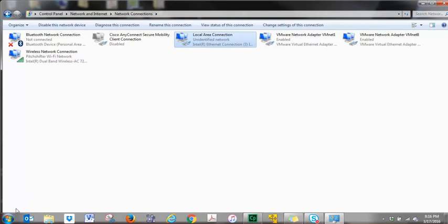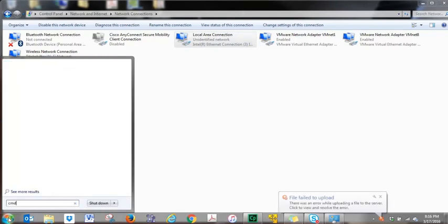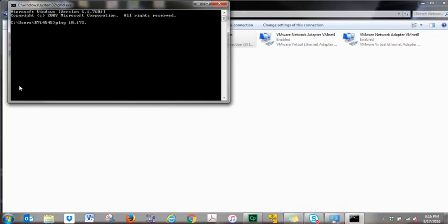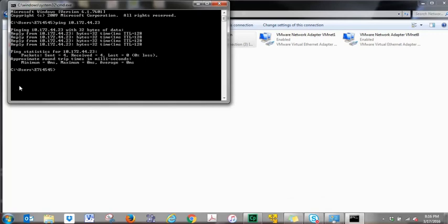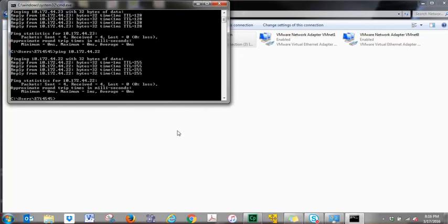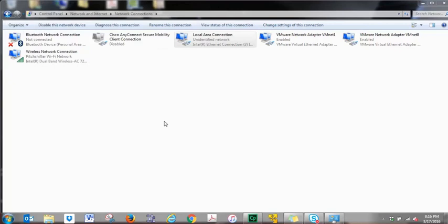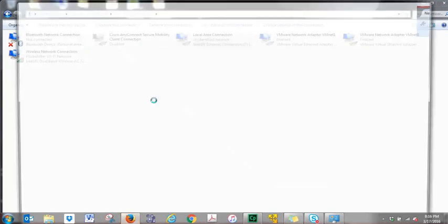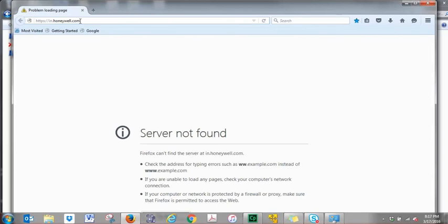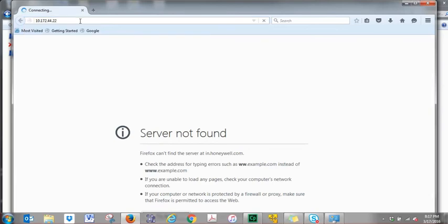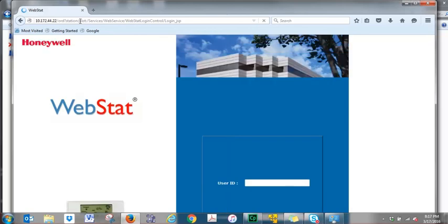Now we want to make sure that the address did stick to our computer. So click on your Windows icon, choose CMD for command prompt, enter. And choose ping 10.172.44.23. And we do have replies. That's good. Now let's see if we can connect to our Webstat, which is 22. And we're getting replies as well. Once you get replies from both your computer and your Webstat, you can open up a browser. And go ahead and type in your IP address, 10.172.44.22. And now you have access to your Webstat.